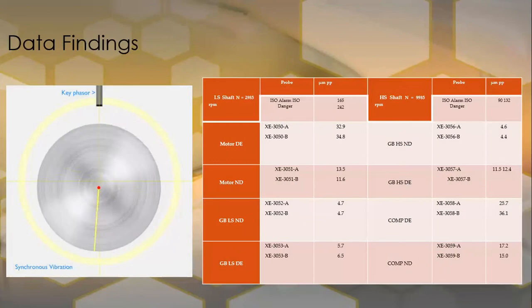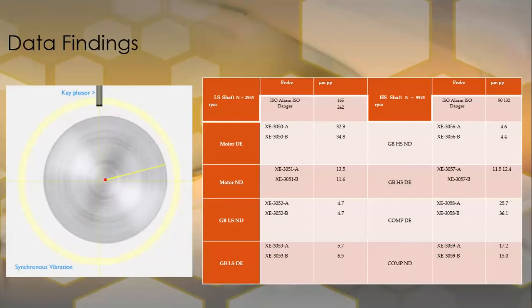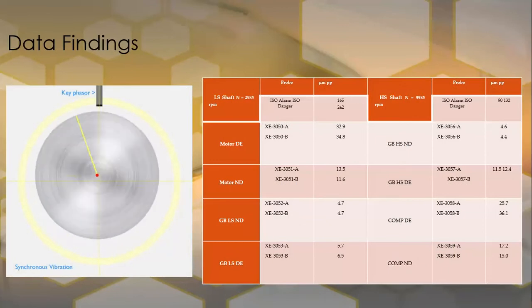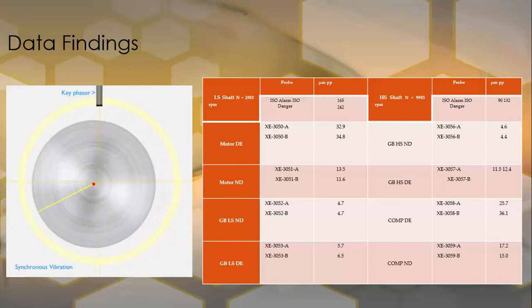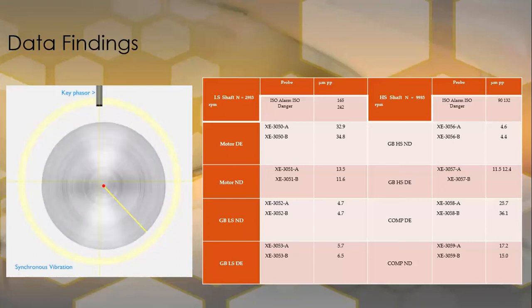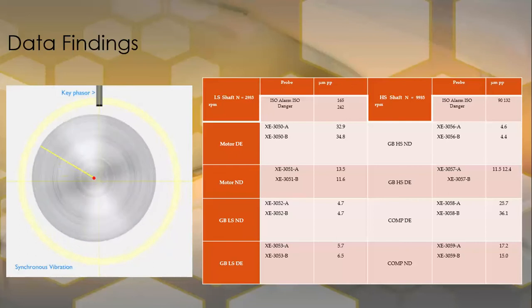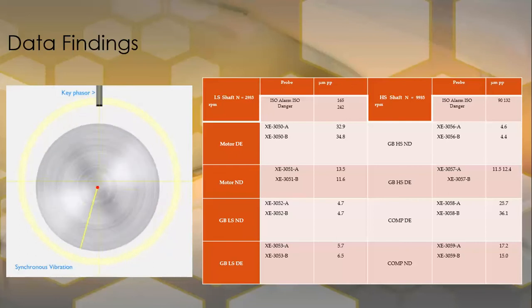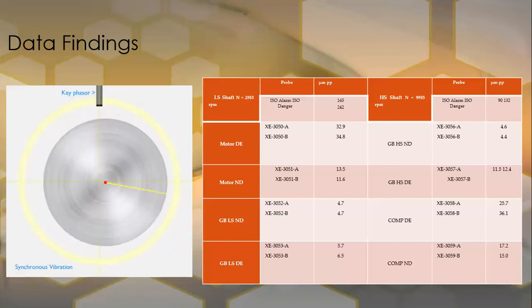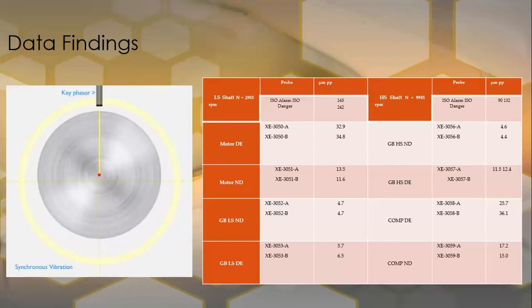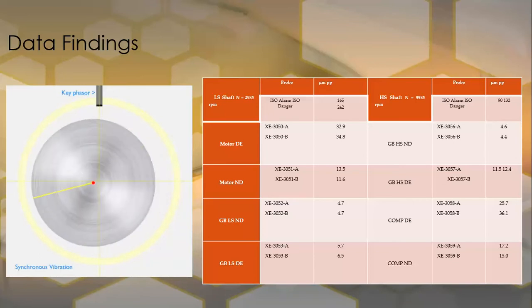This led us to the source of the problem: there is no mechanical fault that could cause a sudden increase in the values and a sudden change in the noise. So we believed that there is an operating parameter that affects the system. Even if there is a mechanical defect, the operating parameters are enhancing this defect.